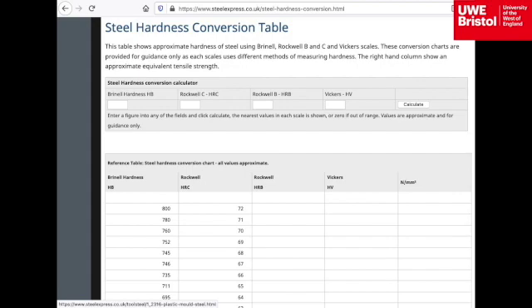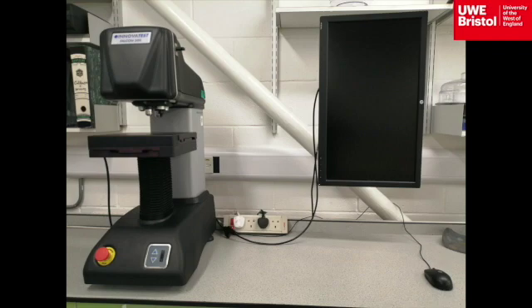Hardness testing can only be done on flat surfaces, as curvature can affect the size of the imprint of the indentation made. Other than that, almost any type of specimen, shape and size, can be placed in a hardness tester, as long as it can fit under the indenter.